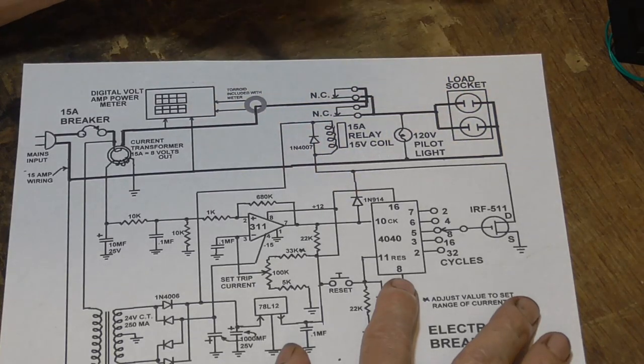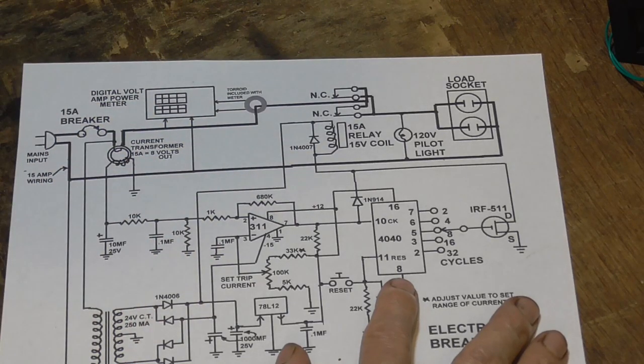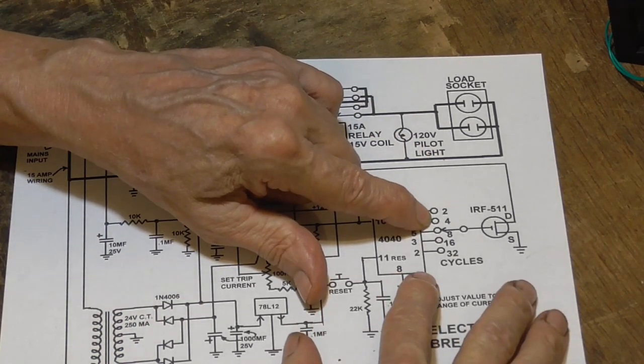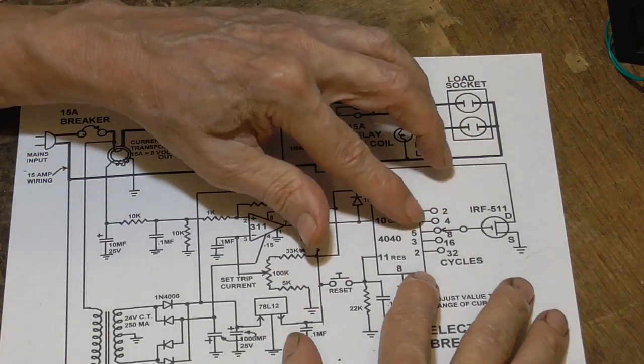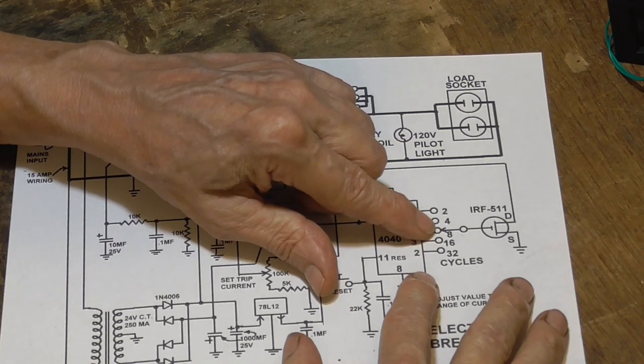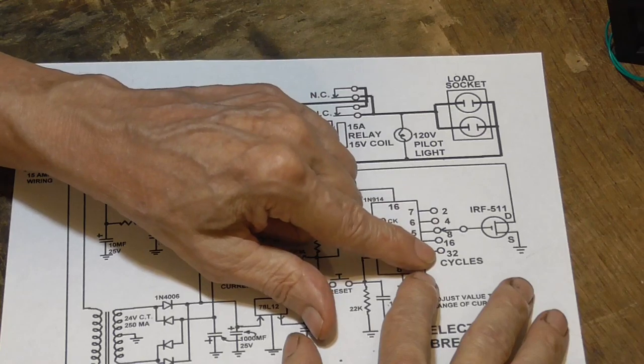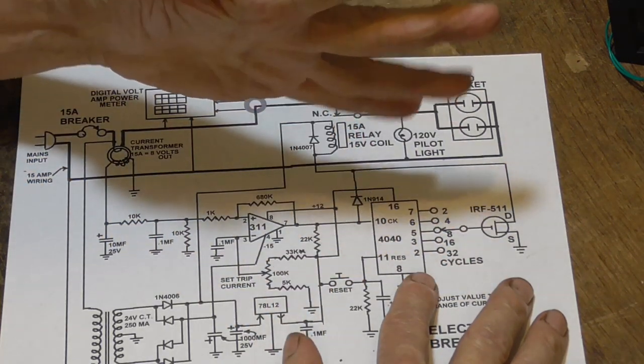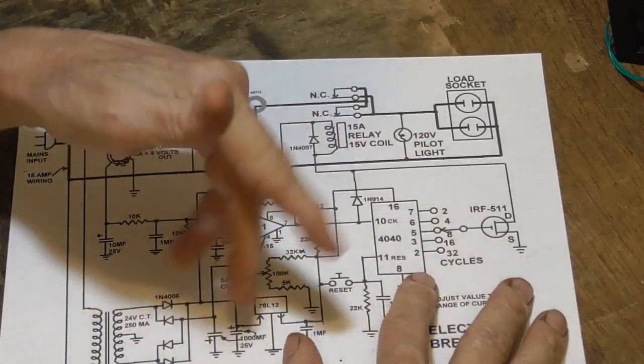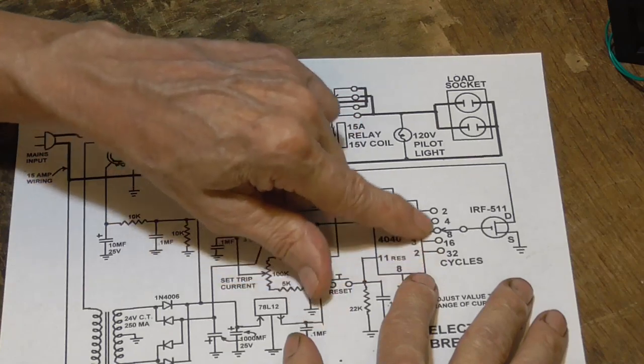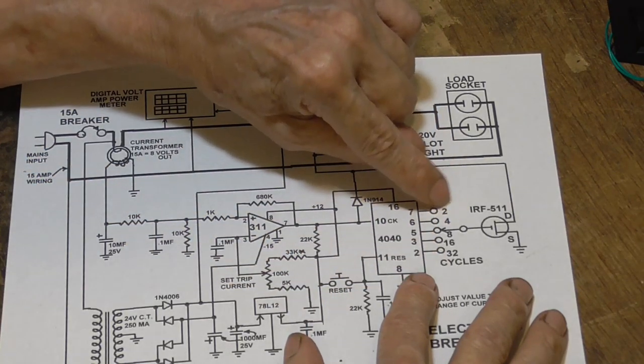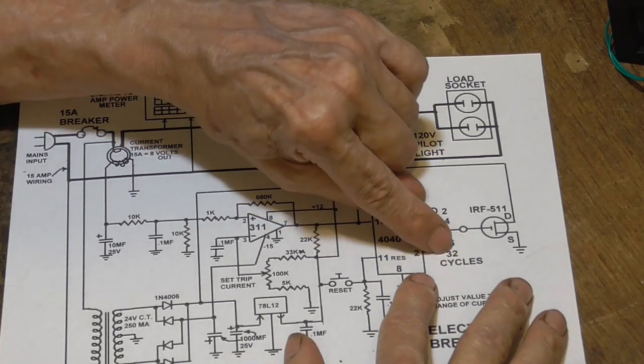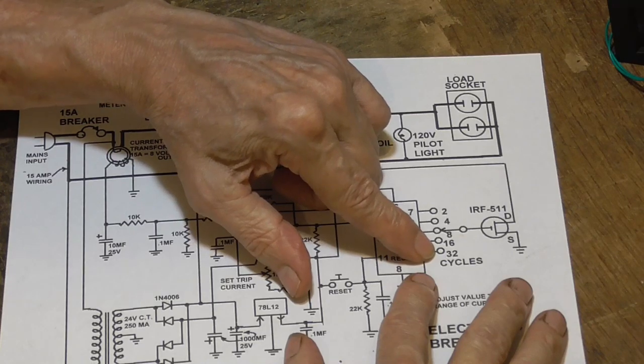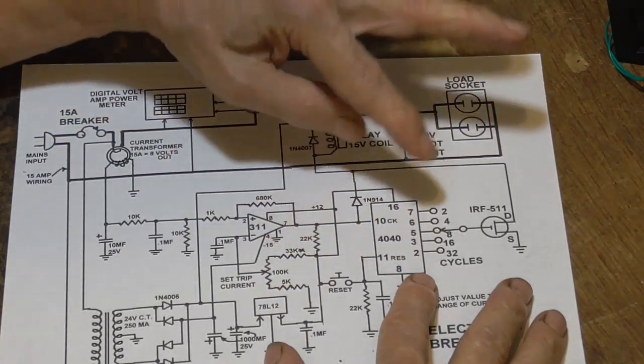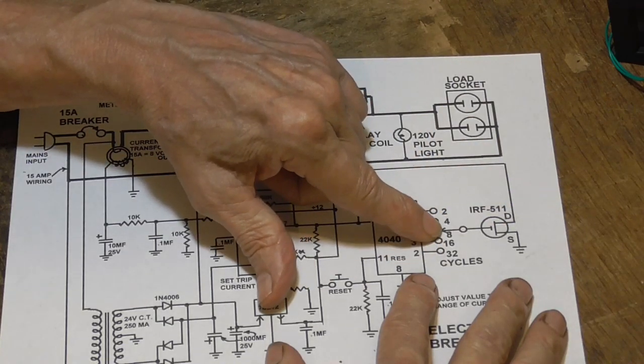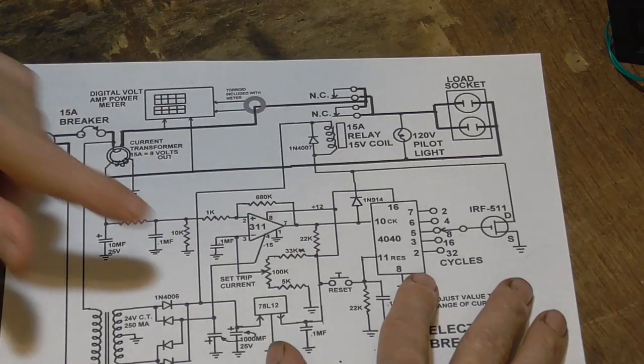That's very fast, extremely fast—as fast as a quick blow fuse. Four cycles would give you about 72 milliseconds. Eight cycles, about 150 milliseconds or so. 16 cycles, somewhere around 300, and 32 would be half a second—since 30 cycles is half a second, 32 is just a bit over. So by selecting one of those taps, we can go from about 30 milliseconds to about 500 milliseconds. That gives us how long we wait before opening the circuit once we go above the set current.